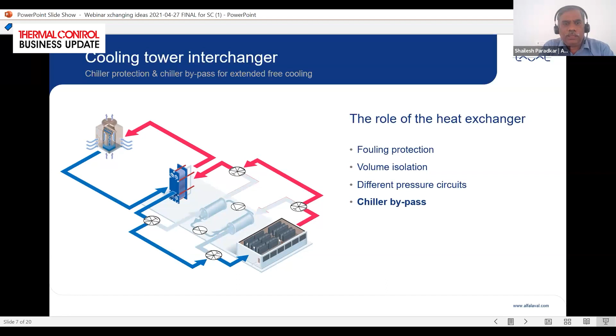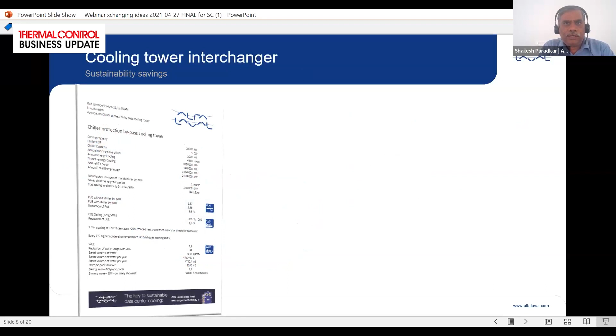One other benefit is that you can have volume isolation of the two circuits. You can also work with different pressures in the different circuits by using the heat exchanger. And one of the most important is that when the climatic conditions are suitable, you can just shut down the chiller and use these plate heat exchangers to directly chill your cooling space. So that's an important aspect. We made some case studies, and even if you estimate one month of chiller stoppage, that gives an excellent benefit in terms of lower energy costs. We have observed almost 7% of your energy bills are reduced by putting this cooling tower interchanger or chiller bypass, what we say, into the system.